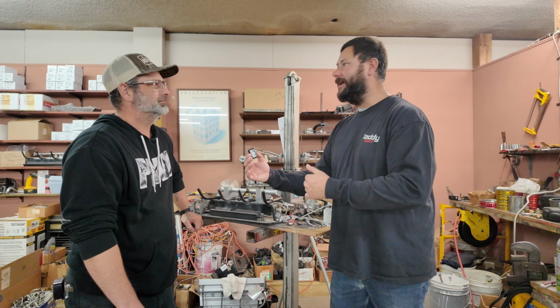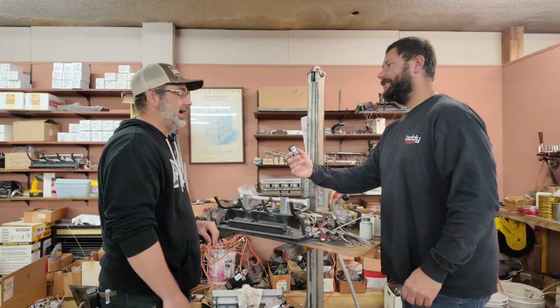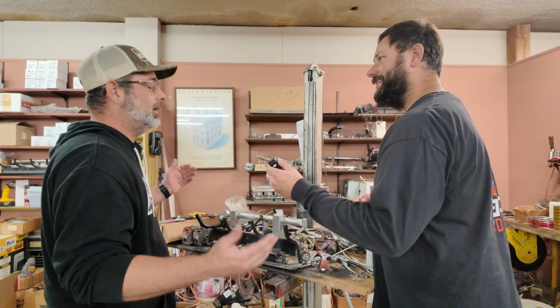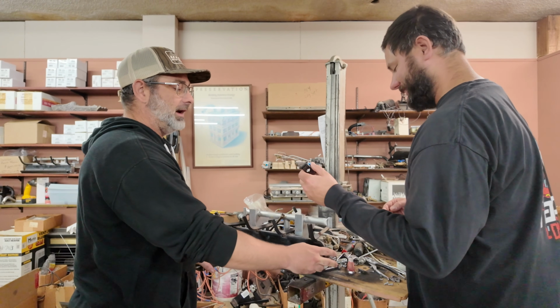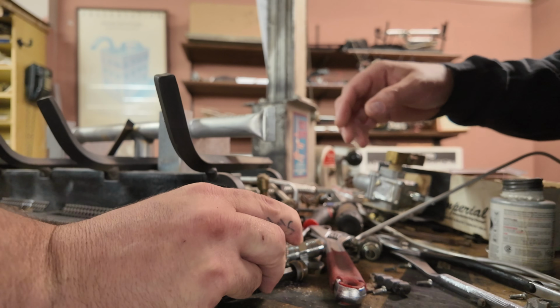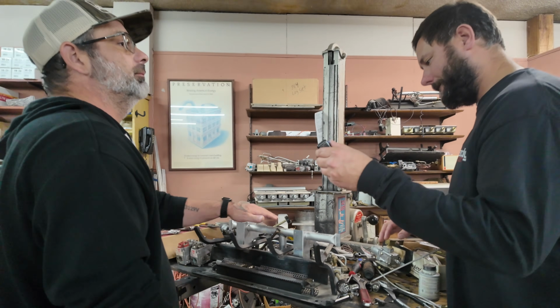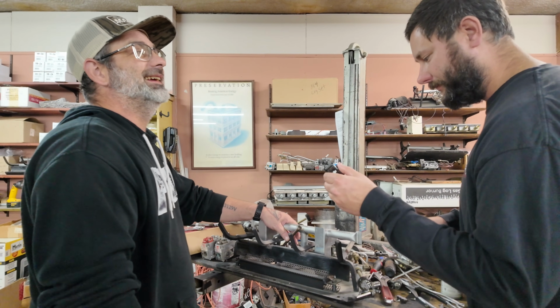Tell me, what does that look like? What is the pilot light? And then what could be the problem? Well, as you know, most homeowners, they don't know. They just say, hey, I turned my knob, I lit my gas, my pilot light came on, and it went out. Got it. The biggest thing is determining which way it is. So if I push in my button and light my pilot light, and as soon as I let go, it goes out completely, usually that tells me it's probably going to be a bad thermocouple system out of it.